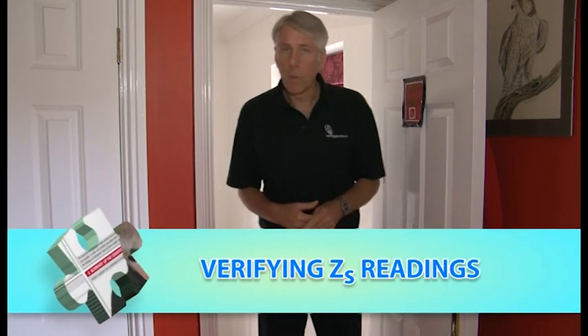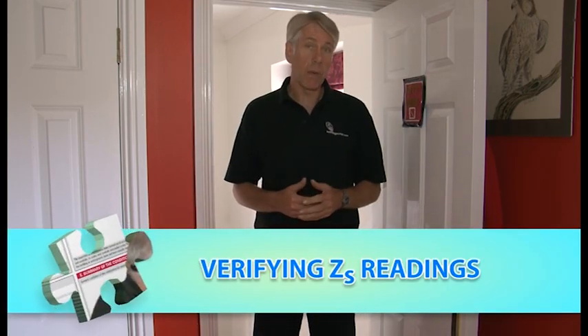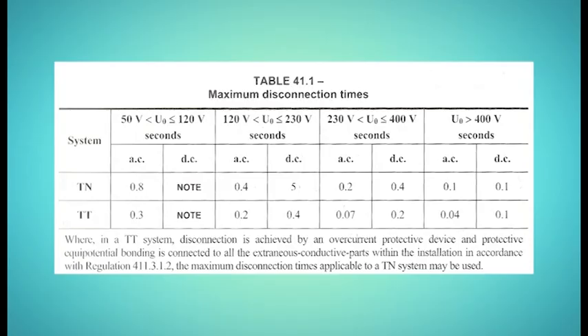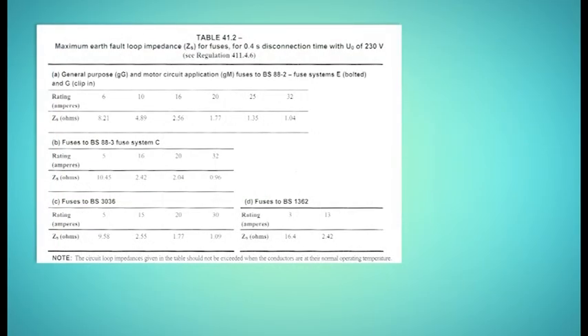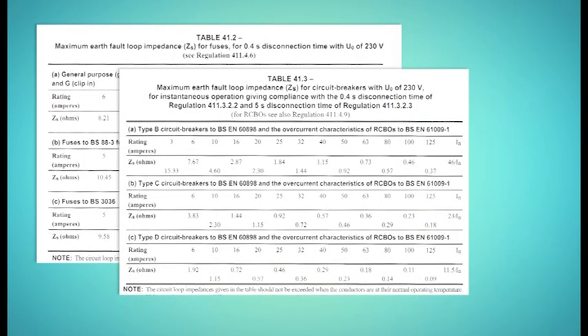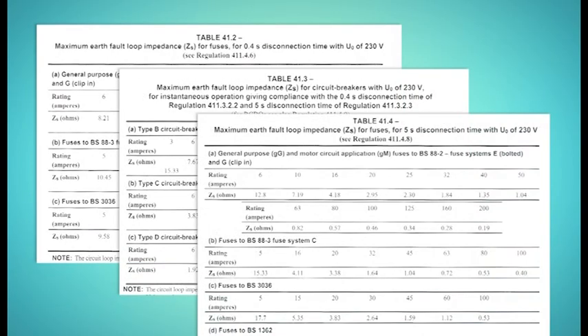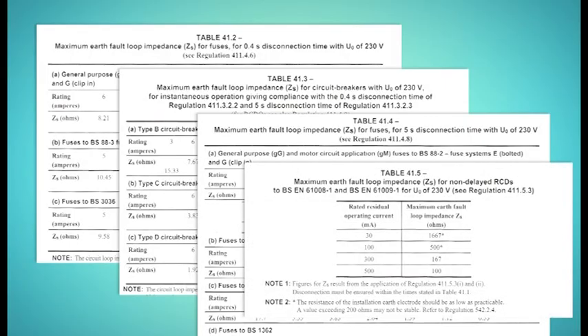ZS is used to determine whether a protective device will operate within the required time when there's a fault between line and earth. For a final circuit on a single-phase TN installation, this is 0.4 of a second. Maximum values of earth fault loop impedance for different types and ratings of protective device are given in tables 4.1.2 to 4.1.5. So for our lighting circuits, we can determine ZS by adding ZE, which we determined during the prospective earth fault current test, to our value of R1 plus R2.